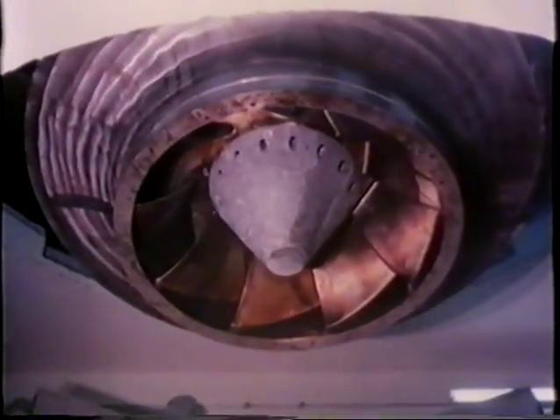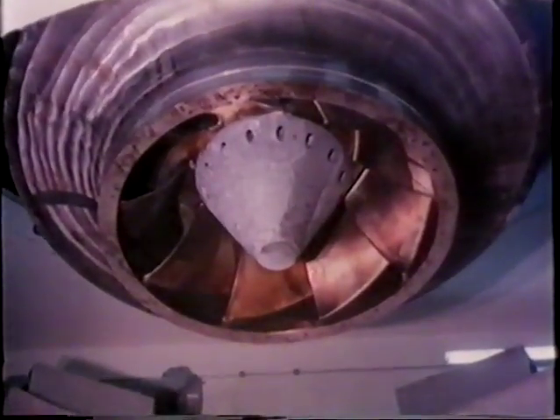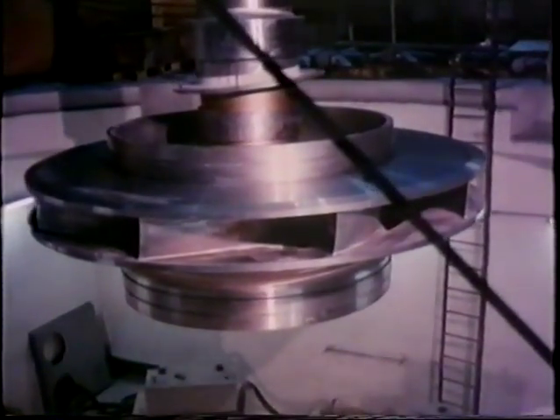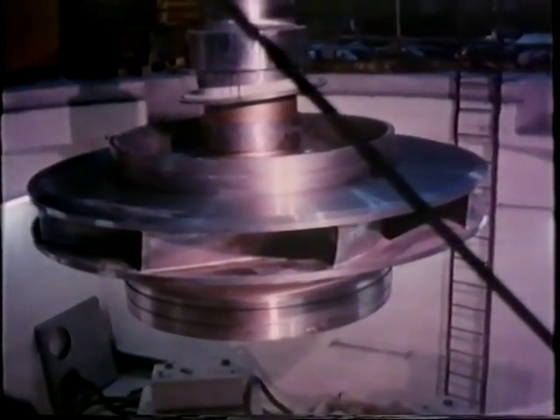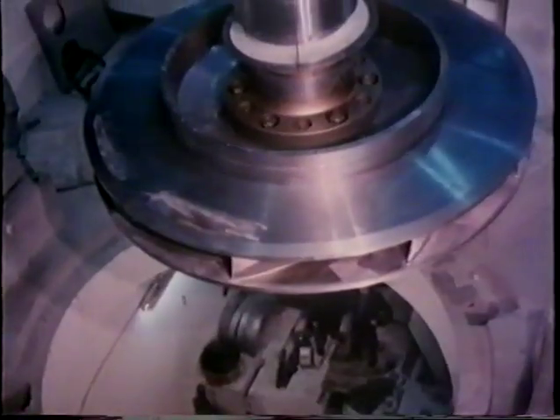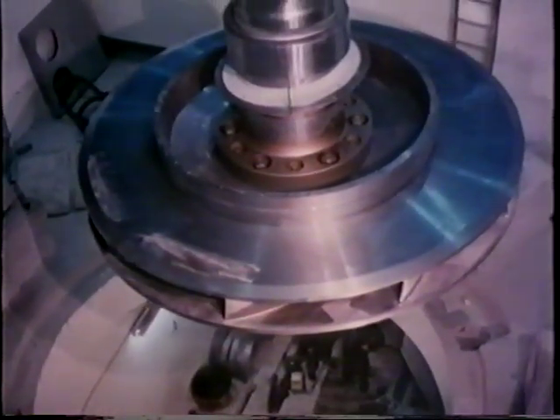The 9-bladed runner is about 3 meters in diameter and 80 centimeters deep. It is cast in 13% chrome nickel steel and weighs about 9.5 tons. Blade profiles were determined by model testing a 250 millimeter runner.